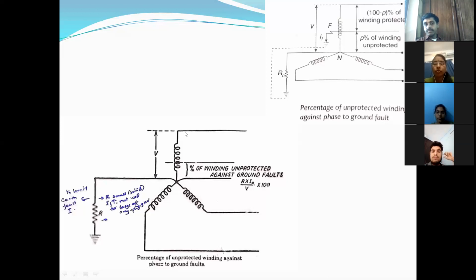That means this phase voltage, phase to neutral, and I naught is the fault current here, where R is the resistance connected in neutral to ground. This resistance is used to limit the earth fault current. If R is small, it is called solid grounding. That means R is almost 0. In solid grounding, the fault current increases, so it is not used for large machines. It is used only for machines up to 3.3 kV.